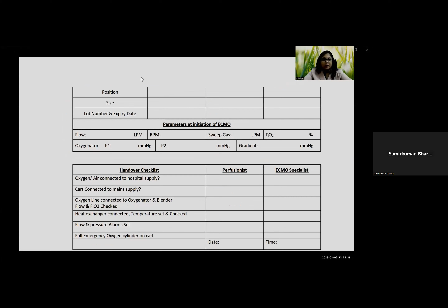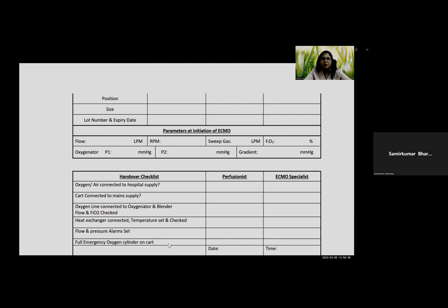And for the handover, they follow this checklist where the oxygen or air is connected to the hospital supply, cart connected to the main supply, oxygen line connected to the oxygenator and blender, heat exchanger connected, temperature set and checked, flow and pressure alarms set, and the full emergency oxygen cylinder is there on the cart. So all these checks are made.